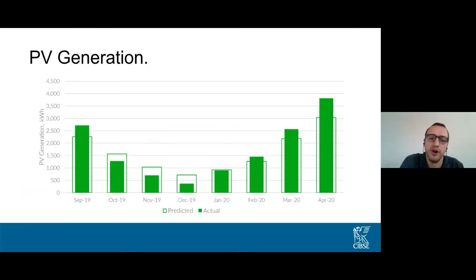This is an example I really like, because it's something I don't think anyone really considers. This chart shows the actual electricity generated by a solar panel array versus what was predicted. The green outline is the predicted generation and the solid green bar is what was actually produced. Looking at October to December, you can see a drop in the actual measured electrical production. Was this because of the weather? Was it because of a fault in the system? Without suitable monitoring in place, you can't know.